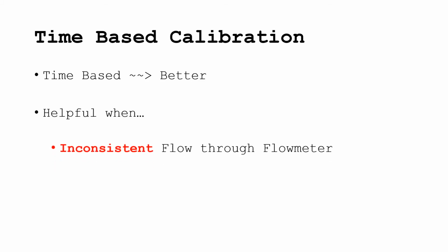Due to certain circumstances, a time-based calibration might be beneficial. For example, if the chemical has an inconsistent flow through the flow meter, or if there is gas in the chemical, time-based calibration would be more accurate.